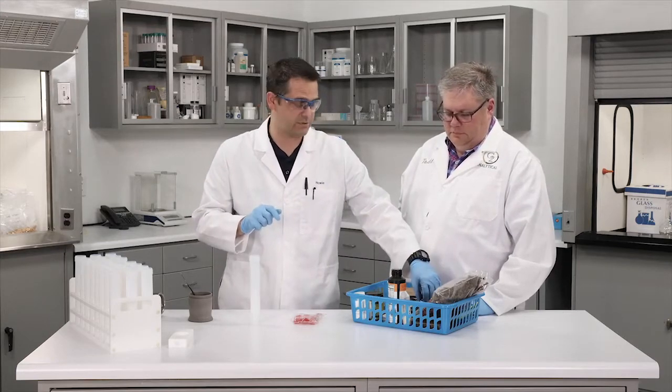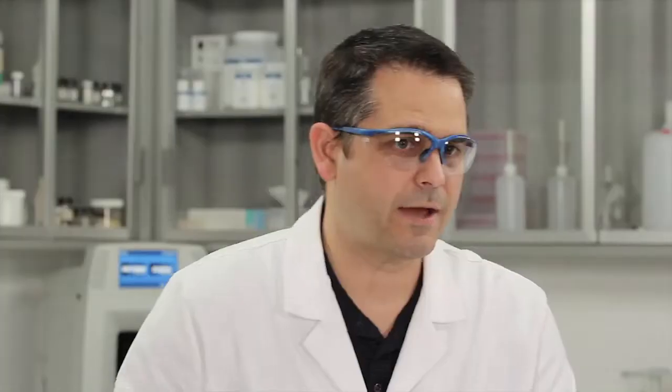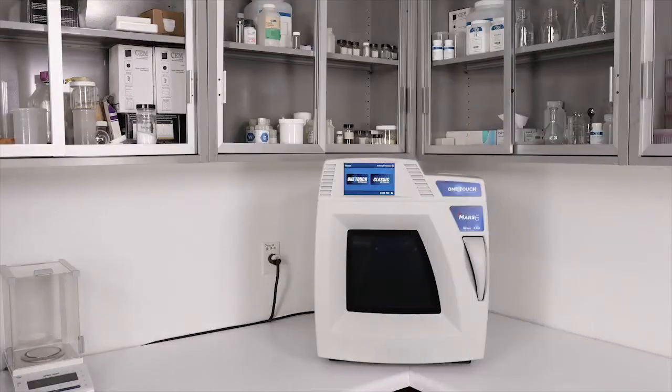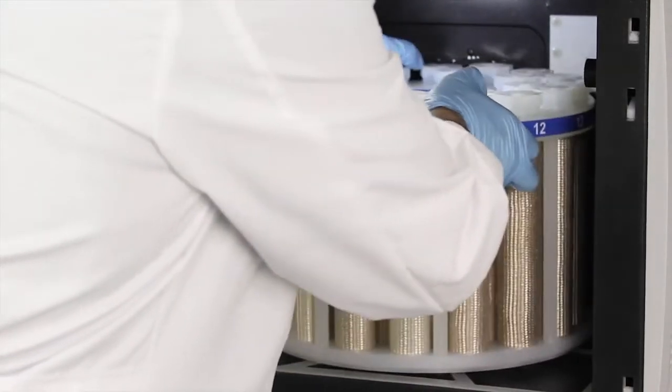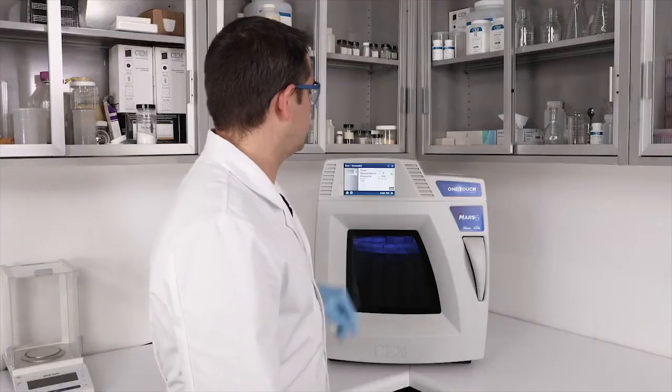The oil is going to be the most challenging sample in this batch, requiring 210 degrees C. Many states, including California, require a half-gram sample size — which is why half a gram was used for the candy and tincture as well. Now that all samples have been weighed out, acid added, and caps torqued down, the EasyPrep Plus vessels go into the MARS 6. Using CEM's cannabis one-touch method: select, press start, and we're done.